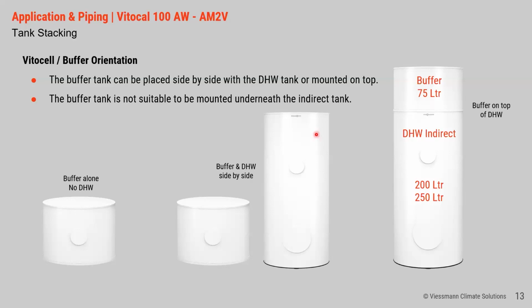So if you are going to use another indirect tank, either a stainless steel tank from us or somebody else's tank, you would need to put the buffer tank on the floor on a rack or something. You wouldn't be able to put it on top. It's only designed to be on top of the tanks that we supplied as matched with the heat pumps. And then again, there's always the possibility that you're not going to do DHW, so your buffer tank would be on its own, like it's shown here.